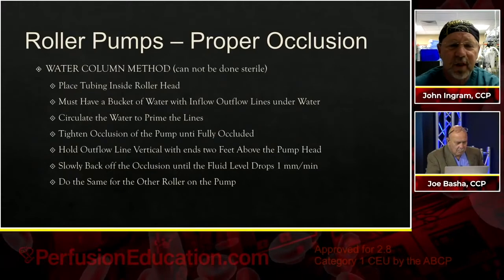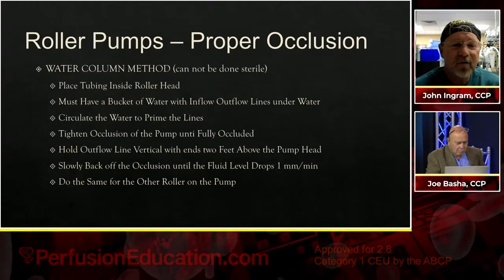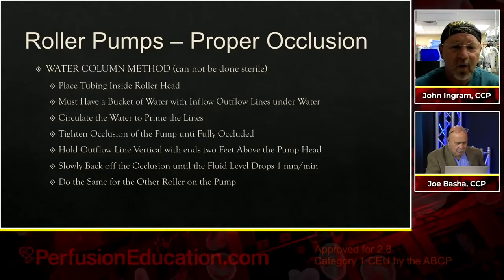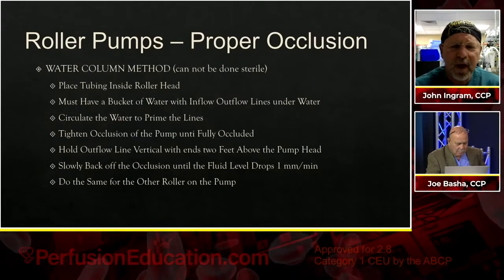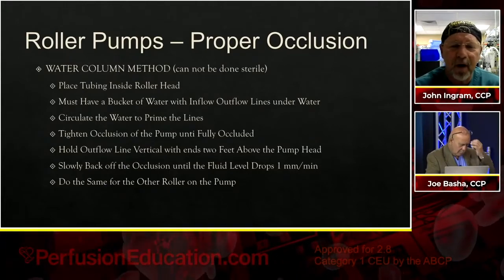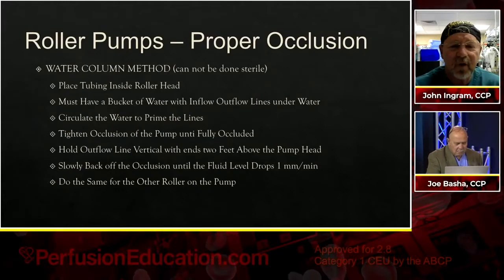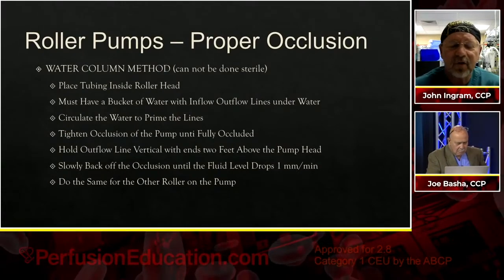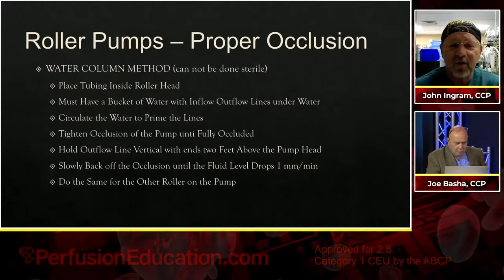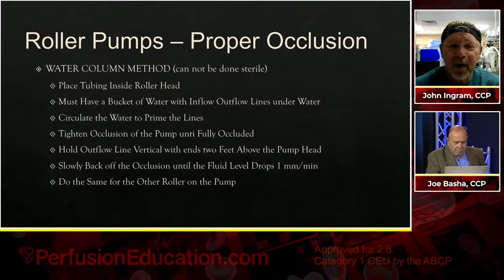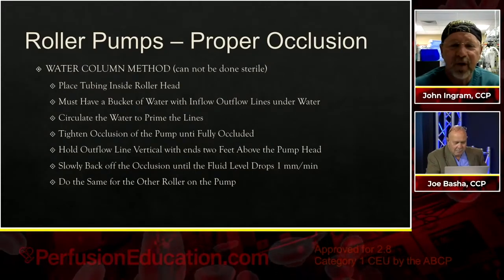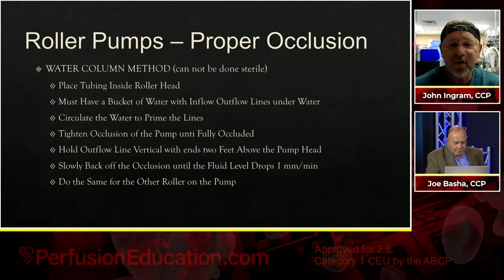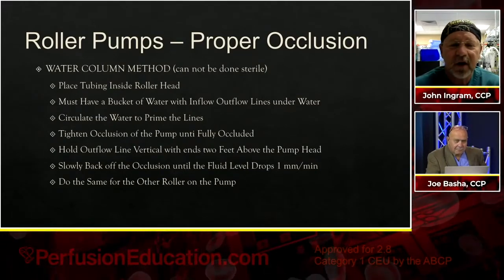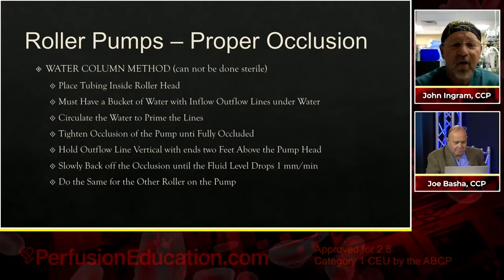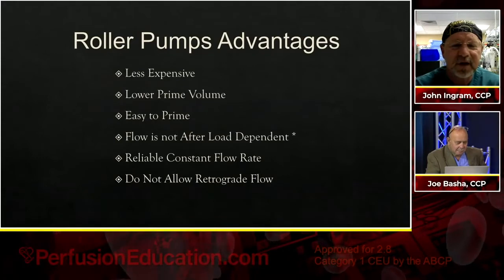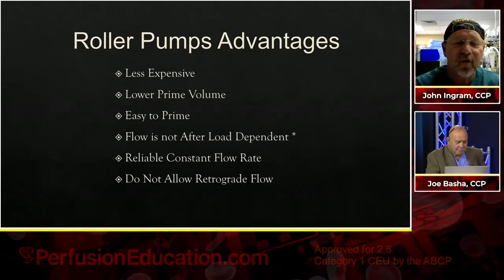You then tighten the occlusion of the pump until it's fully occluded again. Then you take your outflow line and you hold it in your hand, hold it vertical with the ends of that tubing about 2 feet above the level of the pump head. Then you slowly back off your occlusion until the fluid level drops ever so slightly. Textbooks and articles will tell you something like 1 millimeter a minute, which is just barely, barely moving. I don't think anybody could actually time that, but it gives you the idea that you want it to be ever so slightly dropping. And then, of course, try to do the same thing for the other roller on the same pump. This is basically the two styles that people out there use, or versions of them.